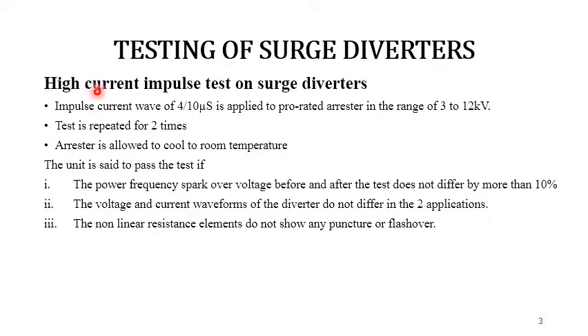Next we have the high current impulse test on surge diverters. This is done on prorated arresters in the range of 3 to 12 kV. A high current impulse wave of 4/10 microsecond peak value, which is mentioned in the specification, is applied to a spare unit of identical castings.